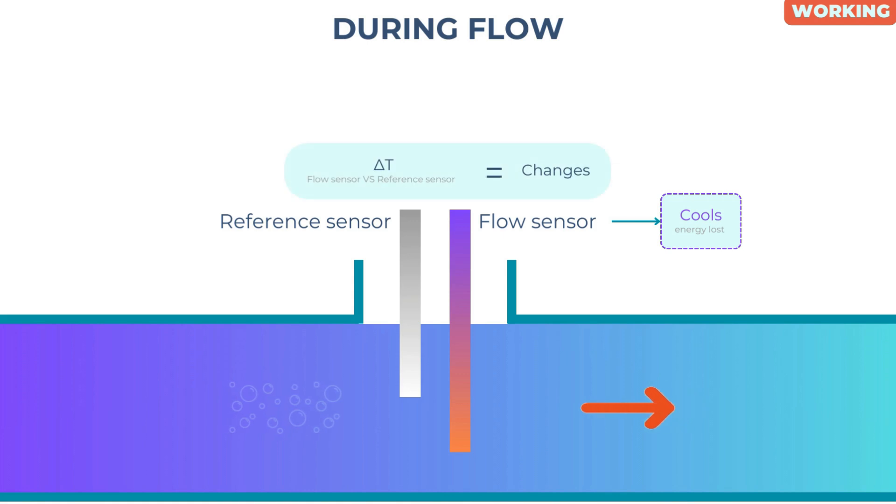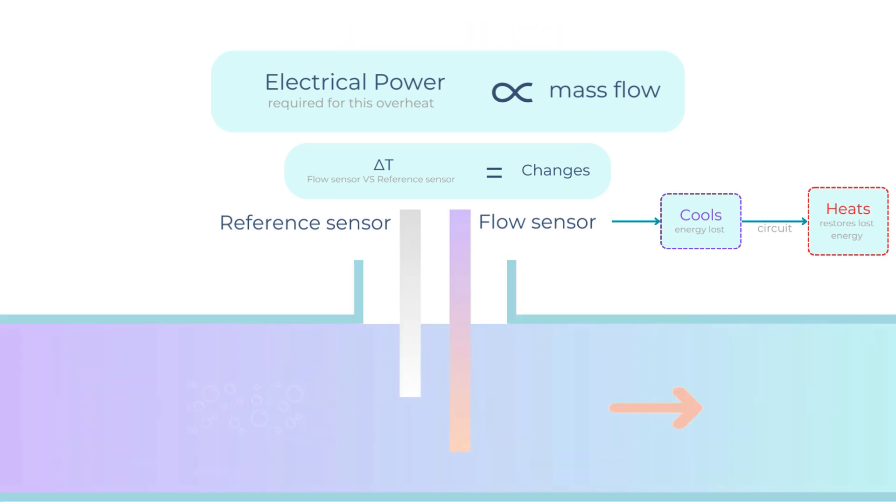The circuit restores the lost energy by heating the flow sensor to adjust the overheat temperature. The electrical power required to sustain this overheat denotes the mass flow signal.